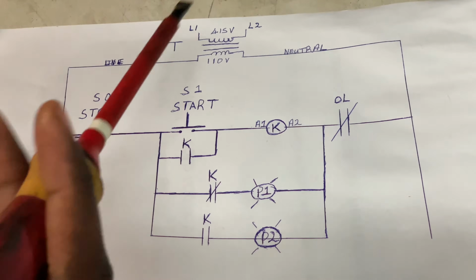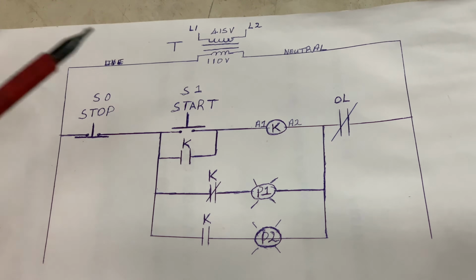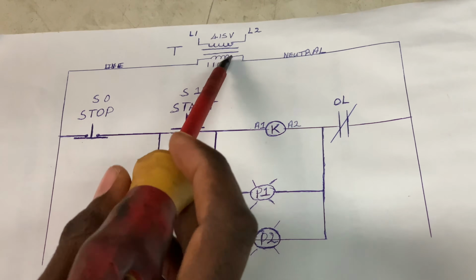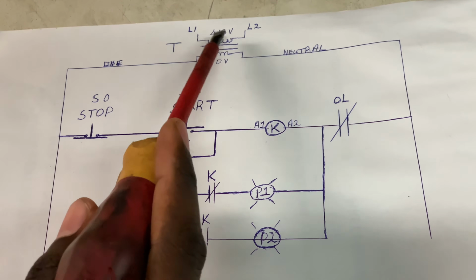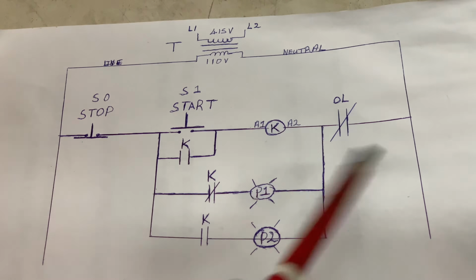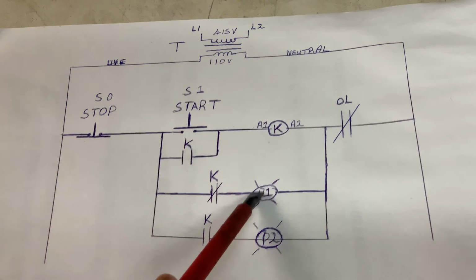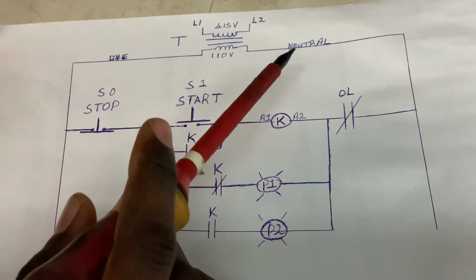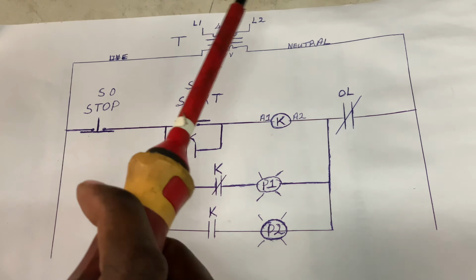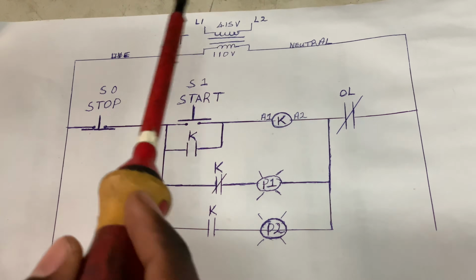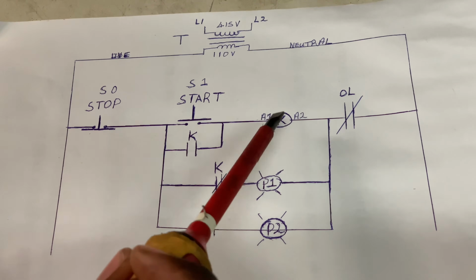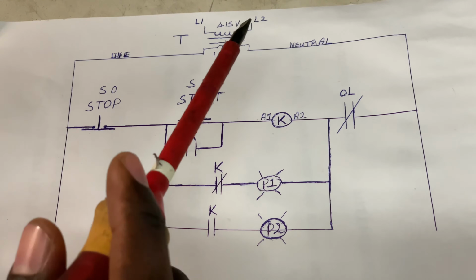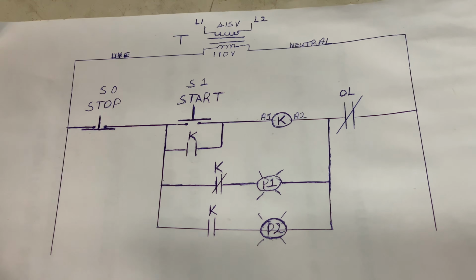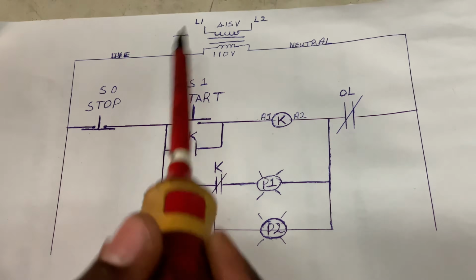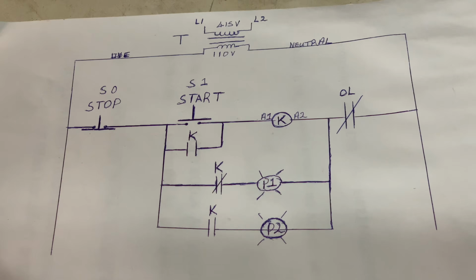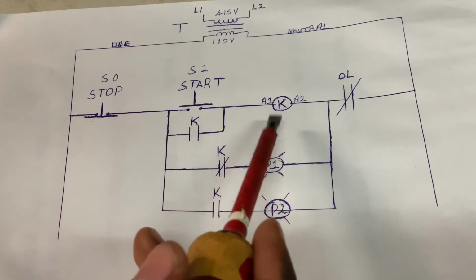Alright, so here we have a wiring diagram of the control circuit. Alright, so this section represents the transformer. The transformer steps down the voltage from 415 to 110 for the control circuit, because the lights and the contactor coil use 110 volts. Alright, so if we never used this transformer and we just took 2 lines and connected it straight to the contactor coil, what will happen is we will have a burnt contactor coil, and then your circuit will not work. The motor will not run if the contactor coil is damaged. Alright, so that is the purpose of the transformer, to step down the voltage to the required voltage of the contactor coil.